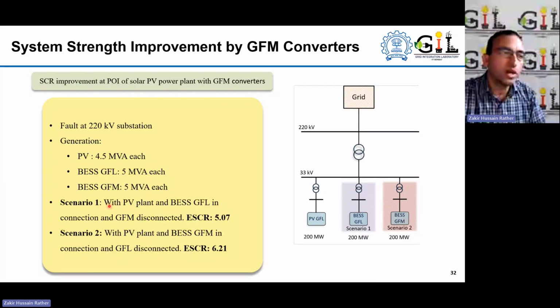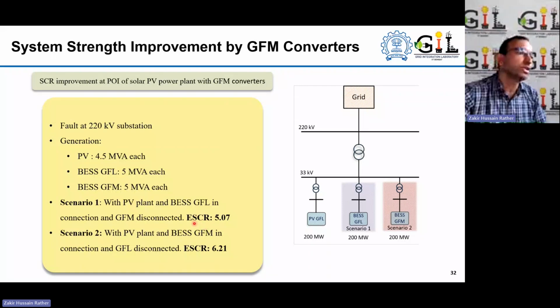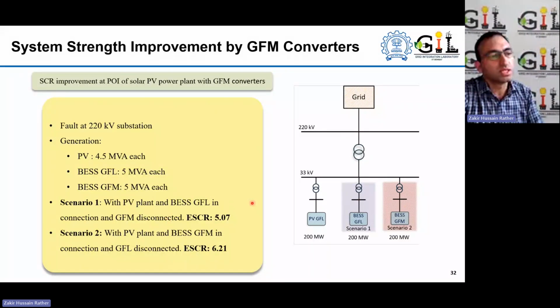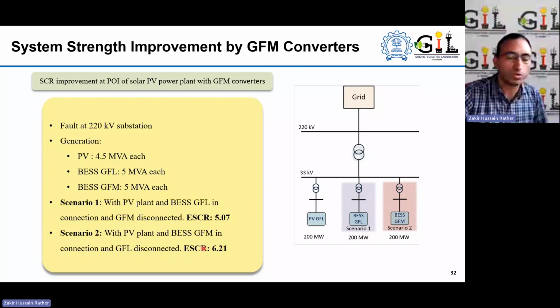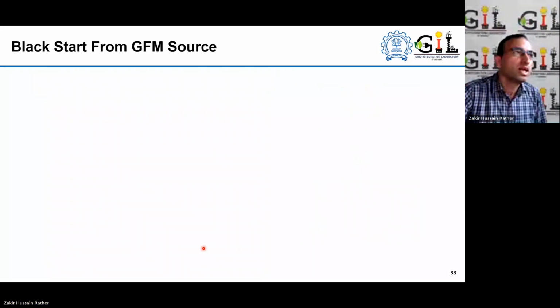In scenario one, where we have the grid following interfacing, we have an effective short circuit ratio at the 33 kV bus of 5 here. But in scenario two, where we have the grid forming technology interfacing this battery energy storage system, in that case, the grid following battery is not active. So for a fair comparison, with this grid forming technology, the short circuit ratio at the 33 kV bus has improved from 5 to 6.21.